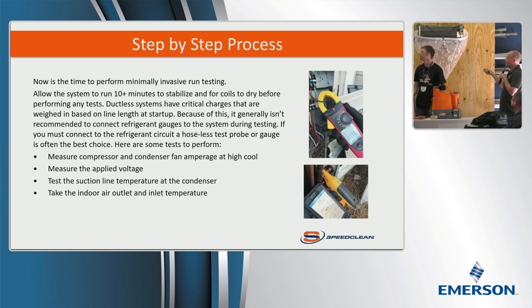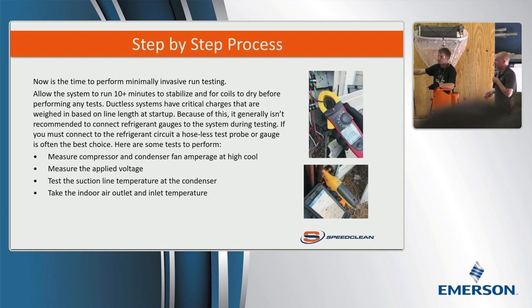So you want to make sure to do that. You also want to make sure to allow it to run long enough for everything to stabilize. The most critical part there is the condenser coil. If the condenser coil is still wet, you can't really test the equipment appropriately. So you need to give yourself in your maintenance 10 minutes for runtime, and that's when you can do your cleanup, start doing your paperwork, do all that, but you got to give it a little time for runtime.